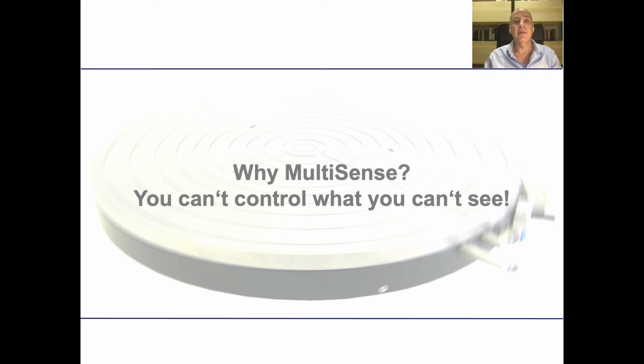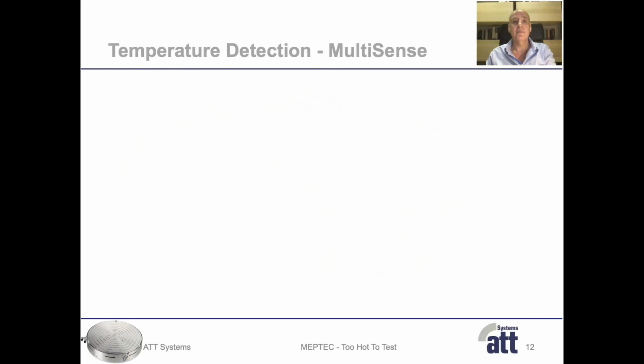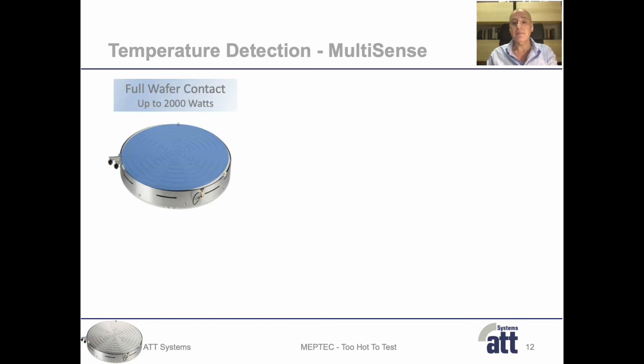The simple answer is because you can only control what you can detect. But let's have a closer look. Let's come back to our three examples. Example 1, full wafer contact testing. Most thermal systems have one control sensor, which is at the center of the chuck. And this is enough for this kind of application because the energy or power is distributed uniformly across the chuck.